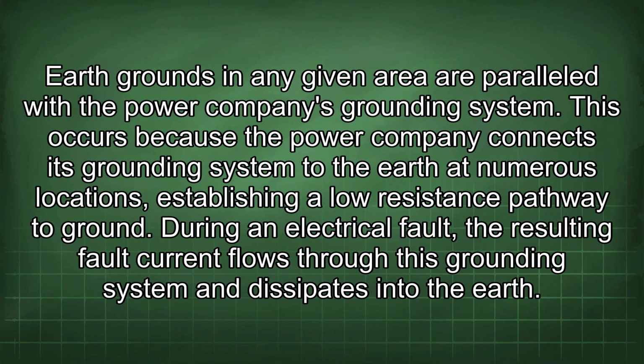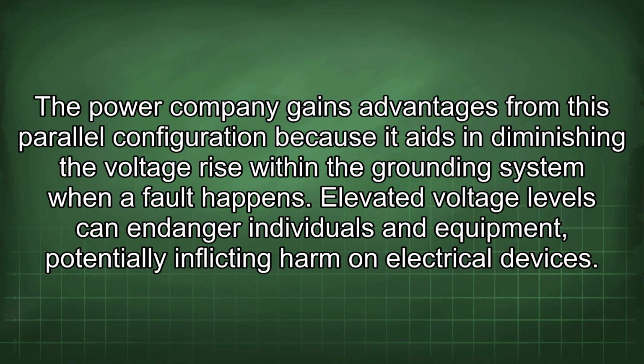Earth grounds in any given area are paralleled with the power company's grounding system. This occurs because the power company connects its grounding system to the Earth in numerous locations, establishing a low-resistance pathway to ground. During an electrical fault, the resulting fault current flows through this grounding system and dissipates into the Earth. The power company gains advantages from this parallel configuration because it aids in diminishing the voltage rise within the grounding system when a fault happens.